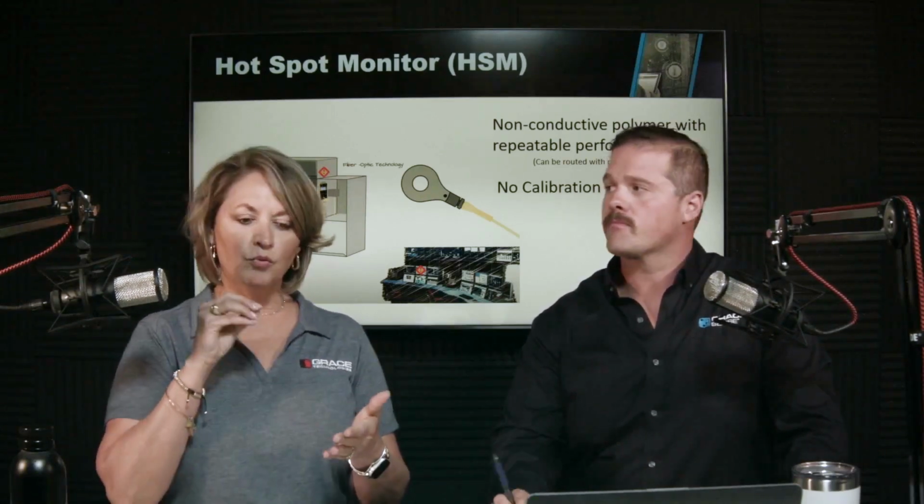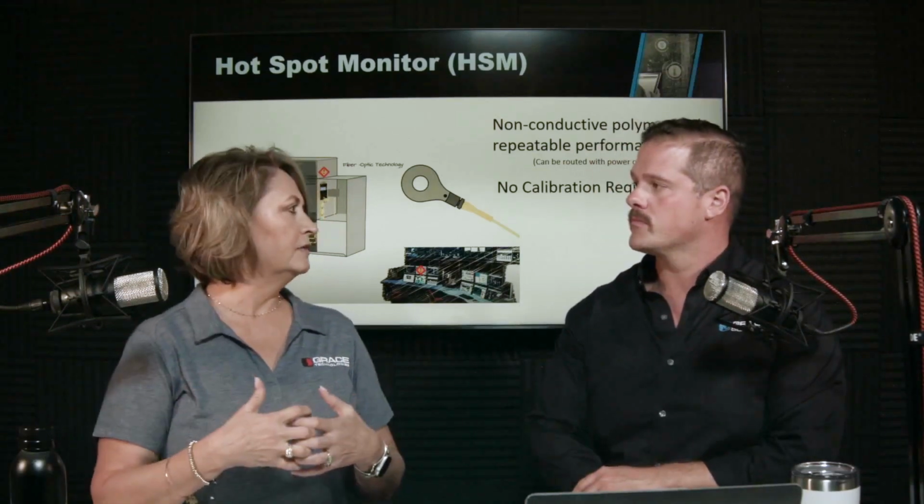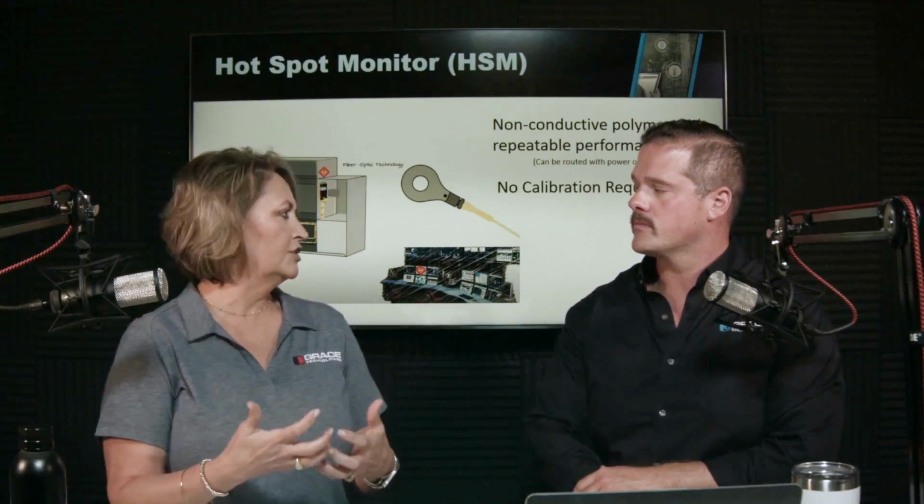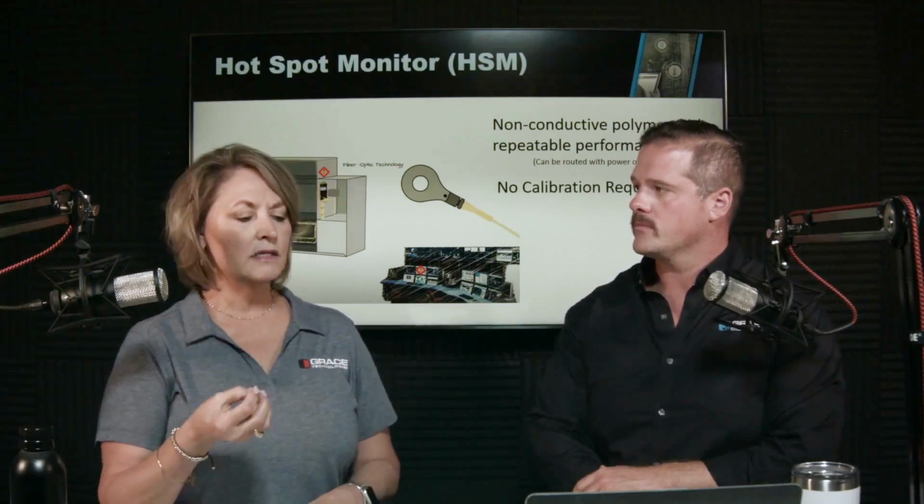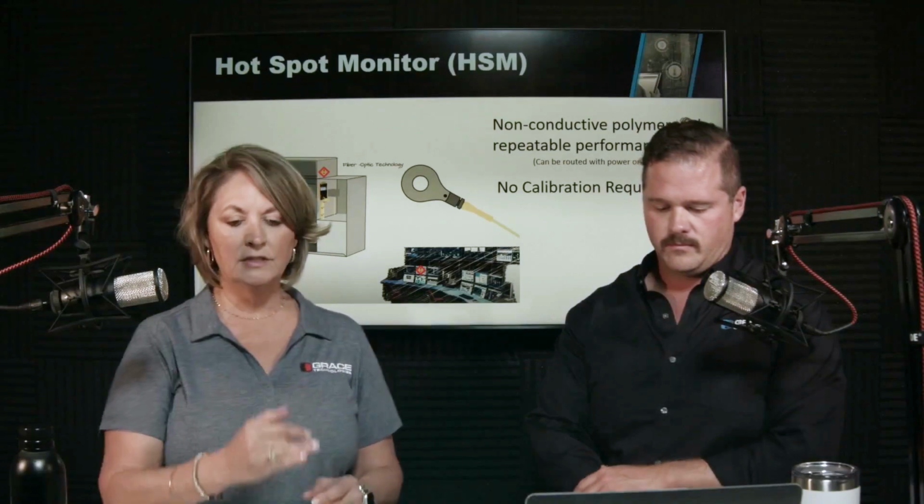So when you look to integrate it into your equipment, including all the way up and through your medium voltage equipment, we know that it has been tested for not only a repeatable performance, but also that because it's a non-conductive polymer fiber, we know that we're getting right on the hot spot. The potential hotspot, we're getting right at those mechanical connections that are the first to have issues. When they have degradation, breakdown, we have loose connections. All those are easily picked up and quickly picked up by a solution like this.